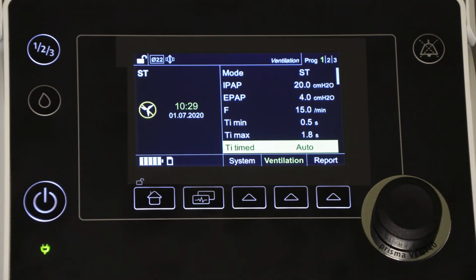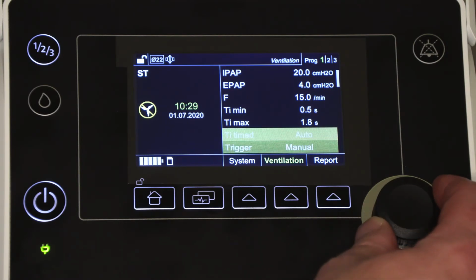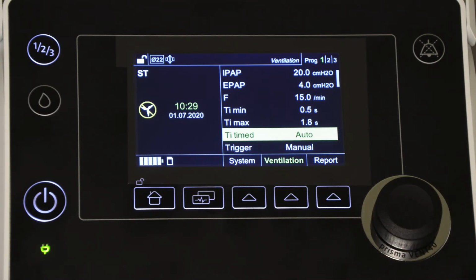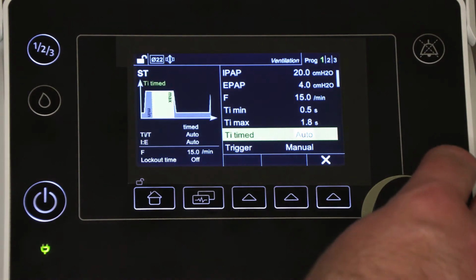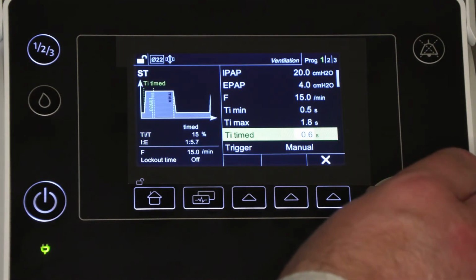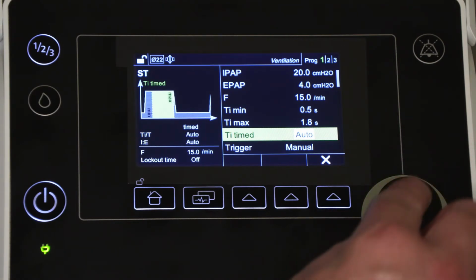The TI time setting will determine how long the inspiration will be for a backup breath only, in the event that the patient fails to trigger a breath in and needs to get some help from the ventilator. This setting can be set to automatic, which will give the patient a timed inspiration which is the average inspiratory time based on the patient's triggered inspirations recorded by the ventilator. Or it can be adjusted and a manual setting can be applied for this backup inspiratory time.